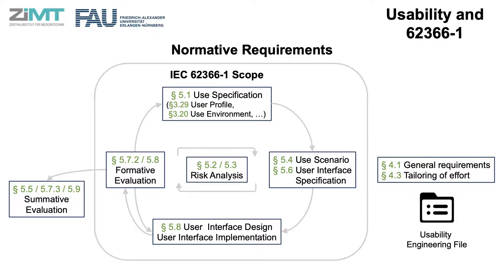Before the device is placed on the market, the manufacturer selects hazard-related use scenarios of the designed user interface to be tested and evaluated with representative users and tasks, designed to measure the effectiveness, efficiency and satisfaction of the complete product. This is called summative evaluation. Formative and summative evaluations shall be documented in respective plans where the manufacturer specifies the protocol of the tests and documents the results in specific reports. The overall result of the usability engineering process shall be stored in the usability engineering file.